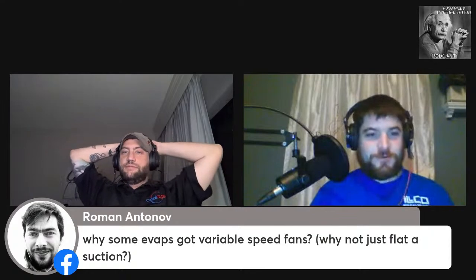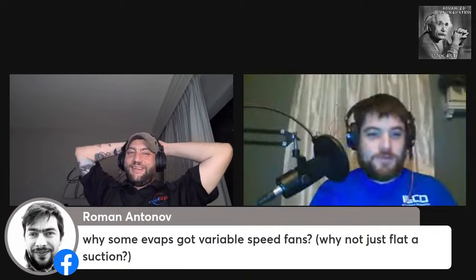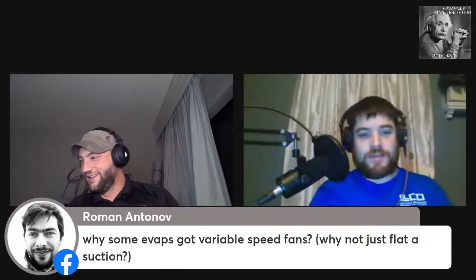Why do some evaporators have variable speed fans? Why not just a flat suction? I'm assuming they're probably trying to goose the UL rating, saying that when it's not actually refrigerating, they're going to slow it down to a second speed. Have you seen those, Kevin? Usually on like the Trenton units. Oh, every new evaporator from Heatcraft has this shit in it, and it sucks ass. It's all I've been dealing with for the last 2 weeks, these 2-speed fan motors, and it is nothing but a nightmare because half the time it's not in any of the RC drawings or any of the EC drawings.